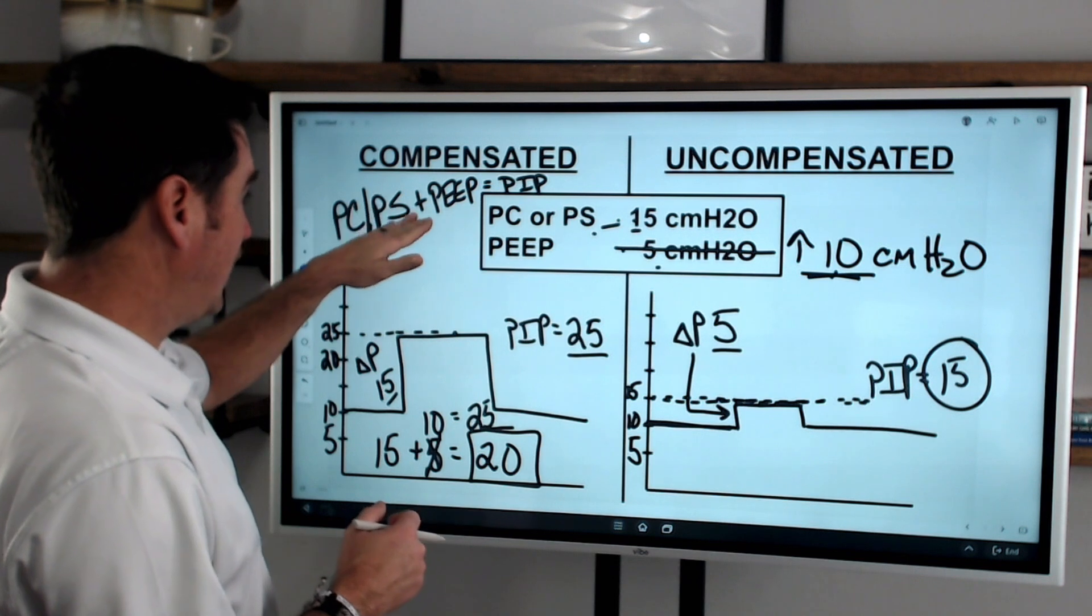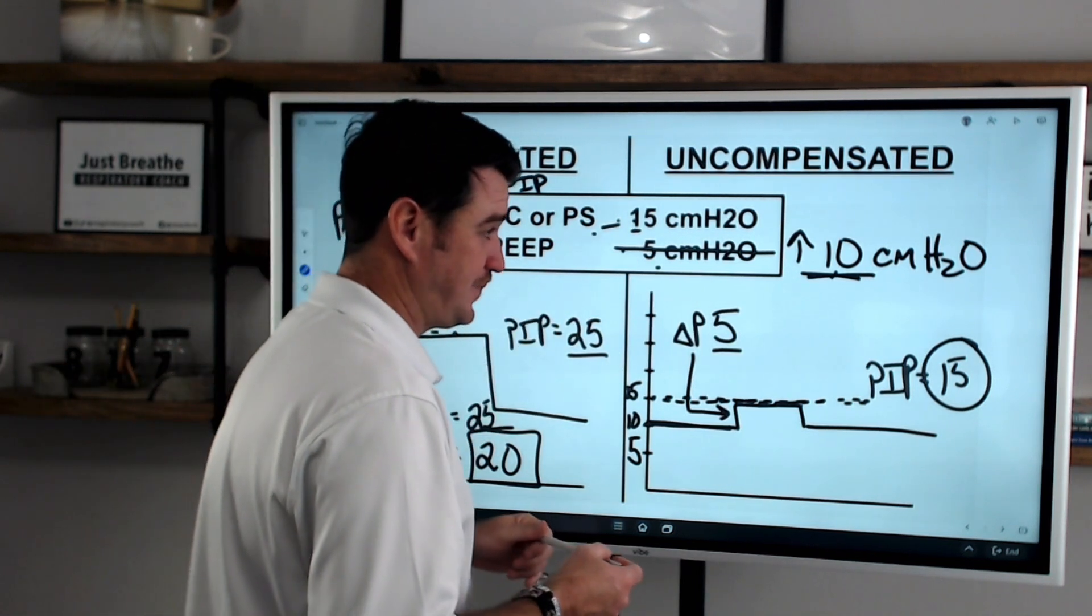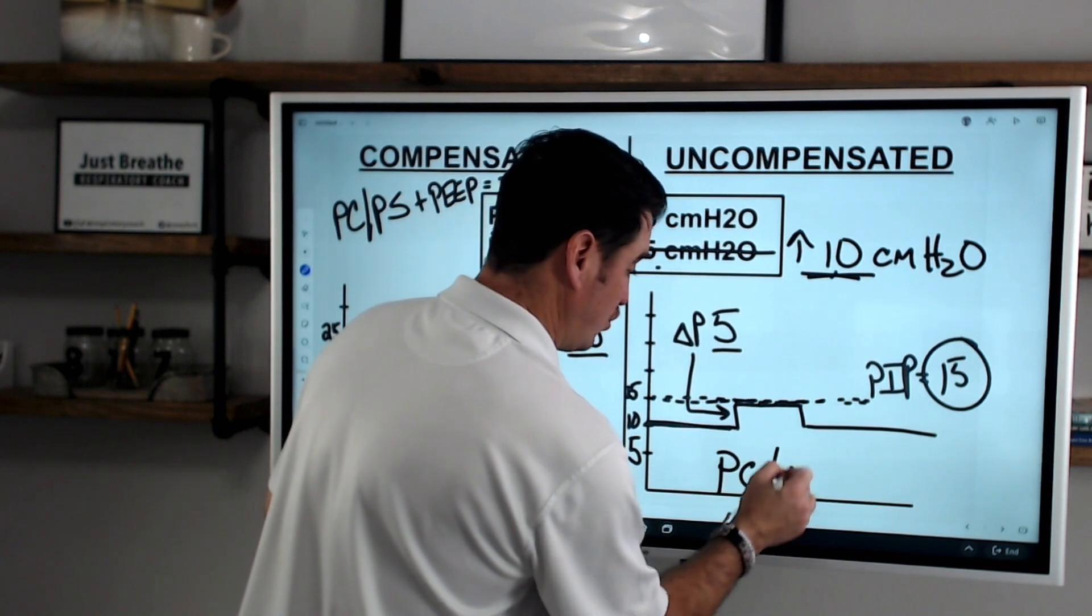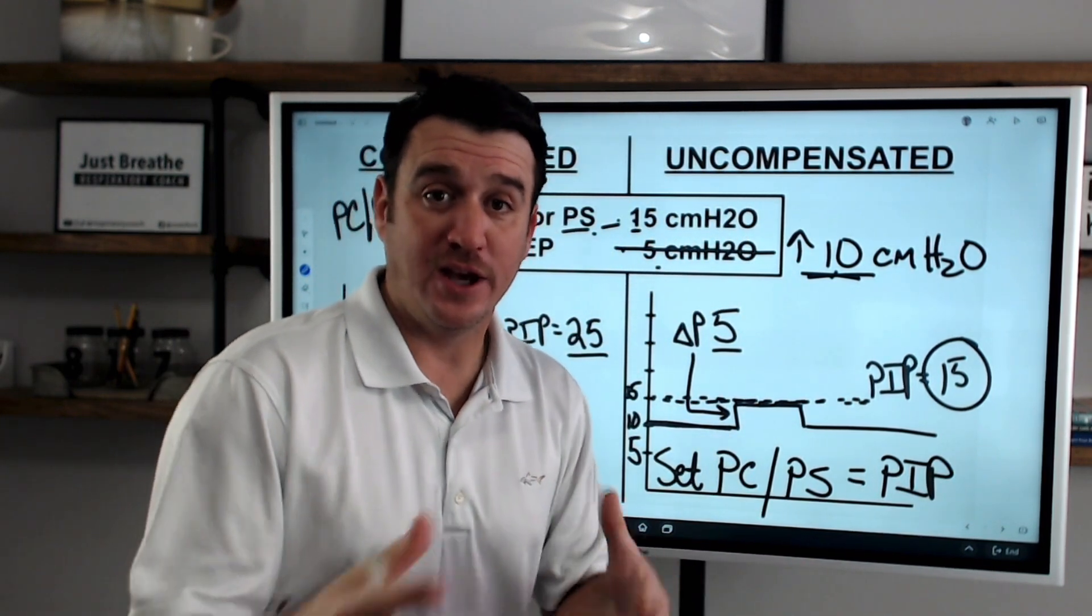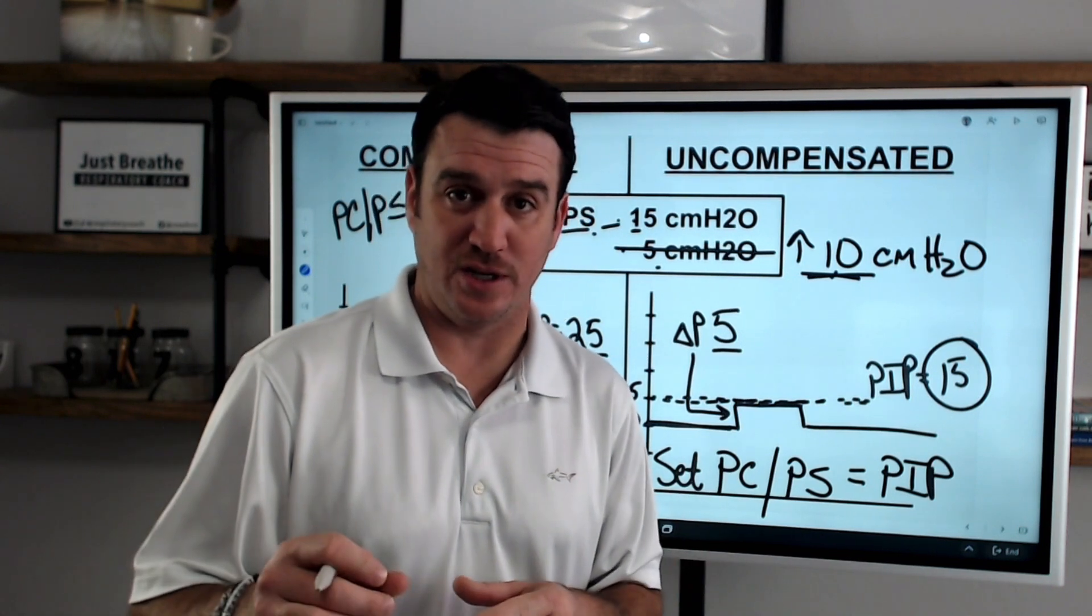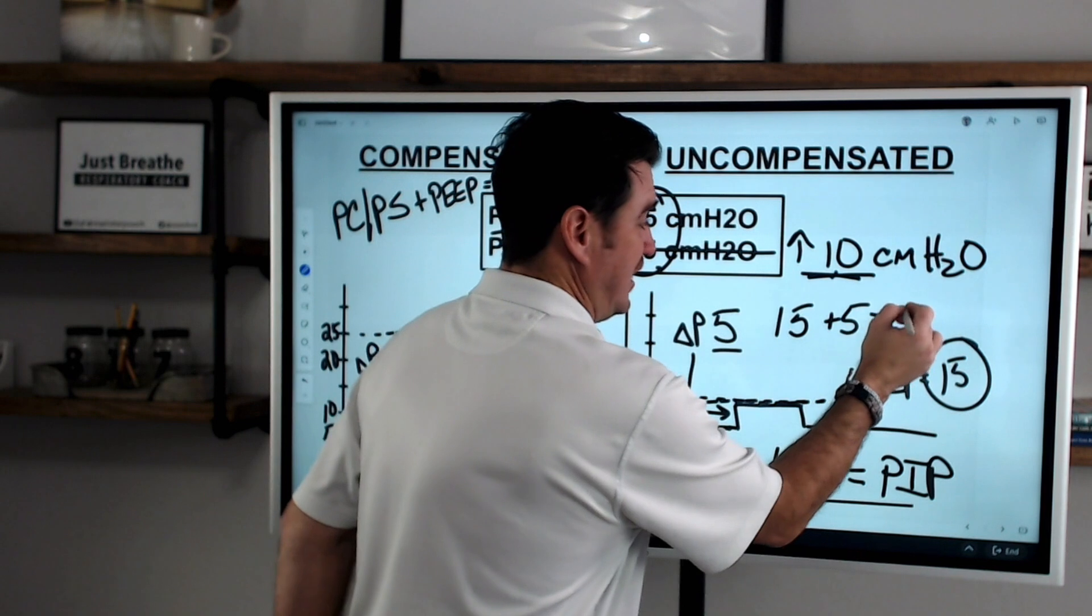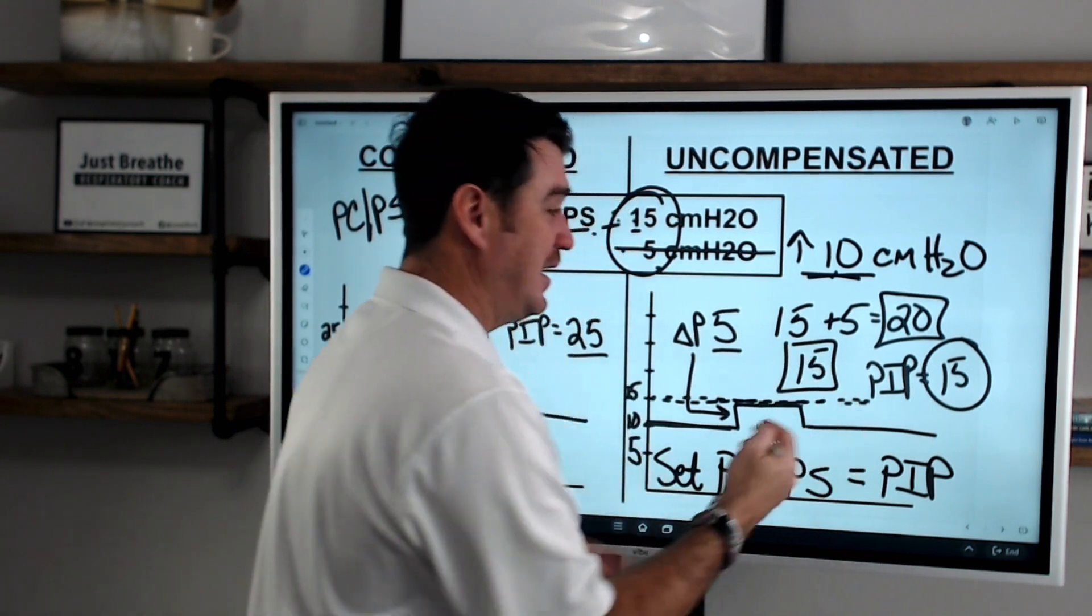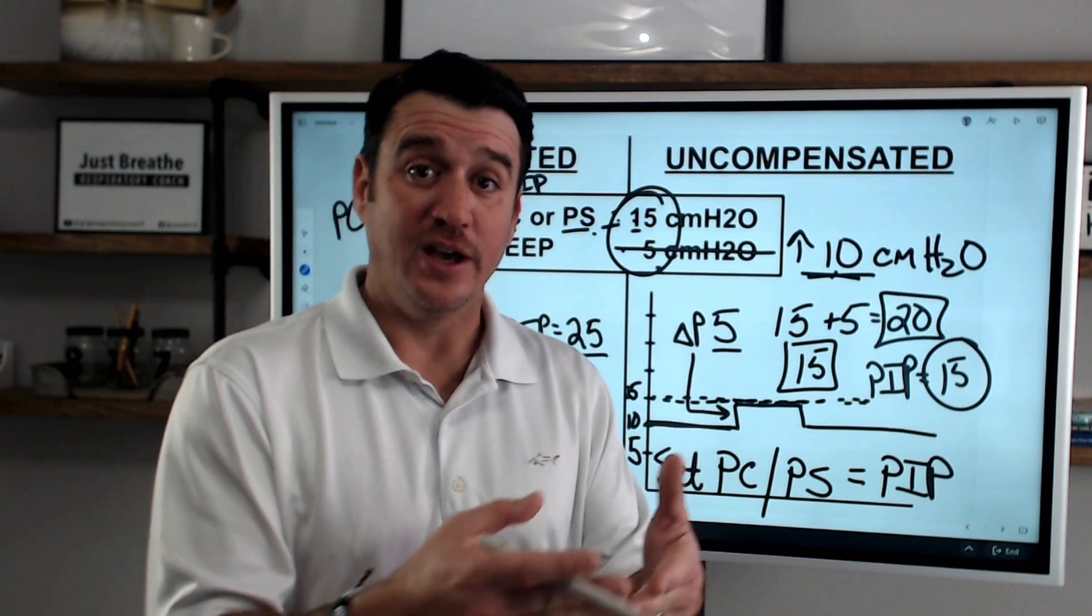If you're working with an uncompensated ventilator, then your set pressure control or pressure support equals your PIP. So it doesn't matter what your PEEP is. Your pressure control, your pressure support is going to cut off when that inspiratory pressure is reached. So if you're on 15 over 5, and you're thinking, oh, I should be at an inspiratory pressure of 20, a PIP of 20, but your inspiratory pressure is only 15, then you know now that you're working with an uncompensated ventilator and you need to double check and make sure that you have your settings set correctly.